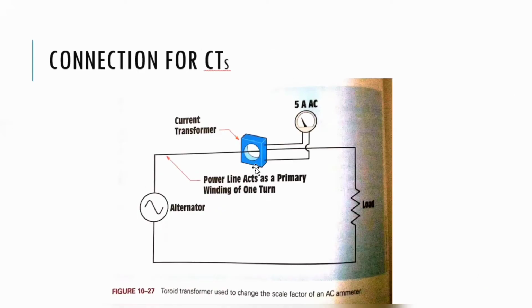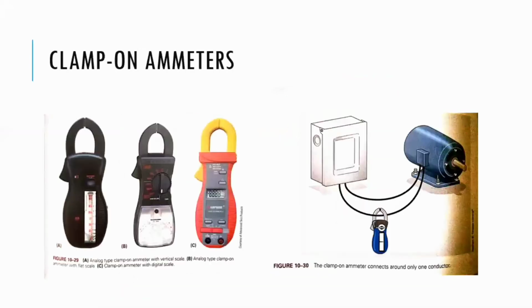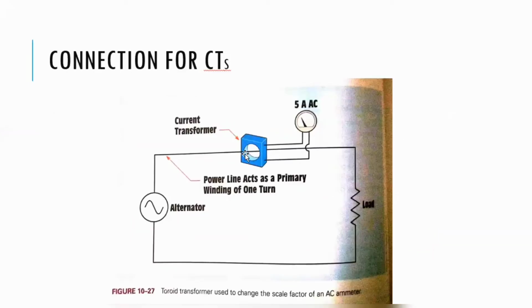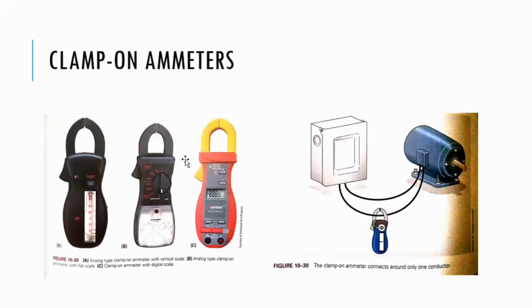This is a diagram of how we can connect the CT to measure the ampere, and the clamp on meter. Here is the CT, and we should pass the wire through this hole. But in this case, we don't need to pass a wire or cut a wire to measure. Okay, this is the analog type clamp meter, which has a vertical scale, which means the reading is measured by the pointer, with horizontal or vertical movement.